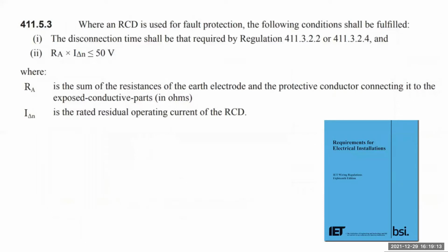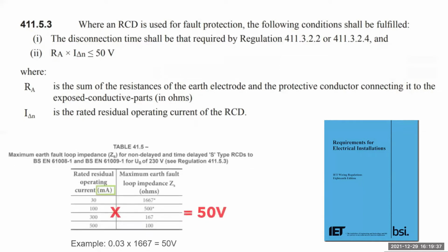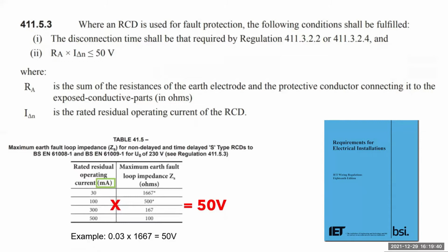BS7671 also states that the touch voltage should not exceed 50 volts, as this is where the voltage is strong enough to push electrons through your skin more easily, which is why we use RCDs to limit the current in a fault condition. On page 64, regulation 411.5.3 gives the formula RA times I delta N is equal to or less than 50 volts. If you then take a look at table 41.5, you will see that they have already calculated the maximum current in milliamps and the resistance you can have before that 50 volt touch voltage is reached.